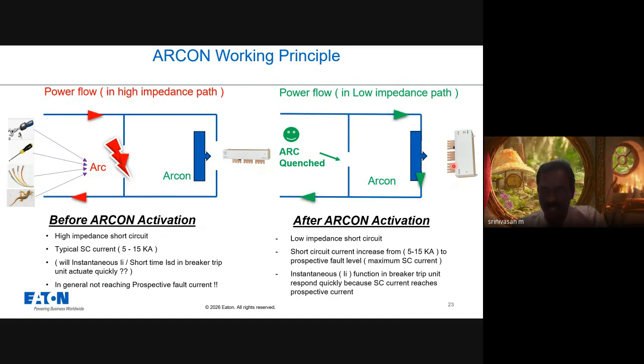the Arcon. By creating the low impedance short circuit, the prospective fault level in the system will increase. For example, the internal arc will generally be between 5 to 15 kA in the majority of cases. After the Arcon makes the low impedance short circuit, it will reach the prospective fault level. For example, for a 1500 kVA transformer, the prospective fault level will be about 36 kA. You can ask the question that the fault current was low, say 15 kA, and now it is reaching 36 kA. But the point to be noted is that the moment the low impedance short circuit is made, the energy which was flowing here to assist the arc to sustain is killed. Our main aim is that the arc should get killed at the earliest. It all happens in less than 2 milliseconds.